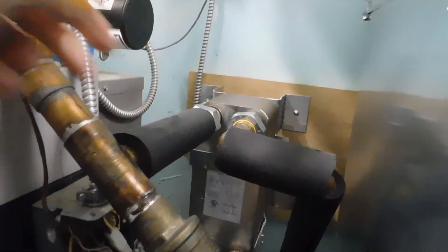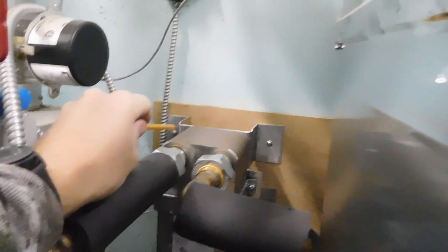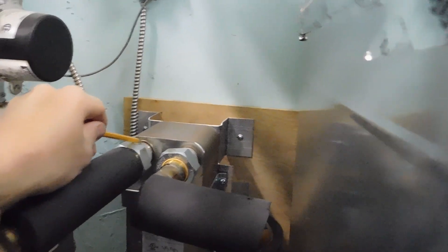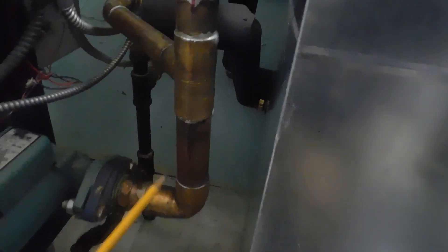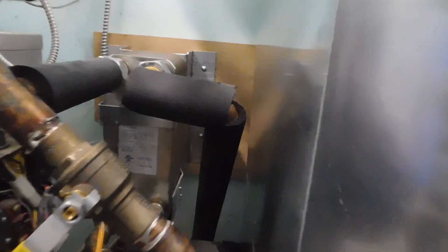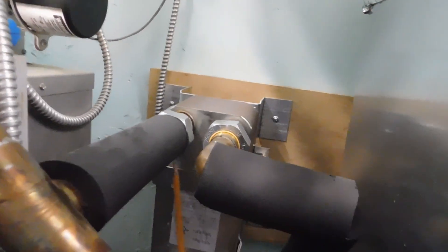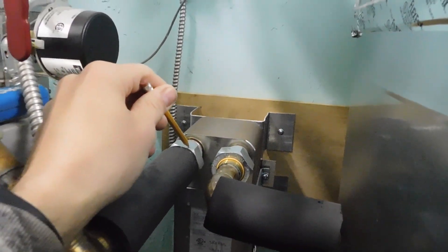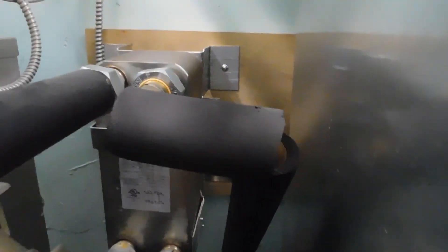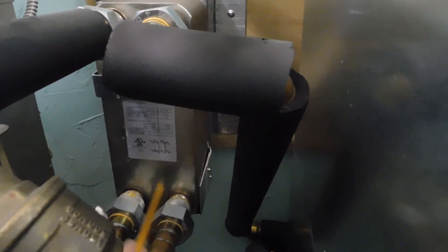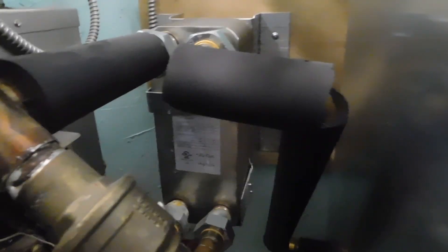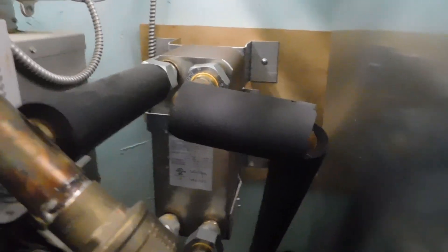So we've got our supply line coming back from the rest of the house. I got a valve in line so that I can force it into the plate exchanger. Goes into the plate exchanger, this is the inlet side, so the cool water returning from the house enters into there and comes out down here, comes back through, and then gets fed into the boiler. Just like the barn, they crisscross. The supply—the cool water supply coming back from the house or the zones within the house—goes in up here, and the hot water coming from the boiler enters from down here. So they basically cross paths going through the different plates in the plate exchanger.